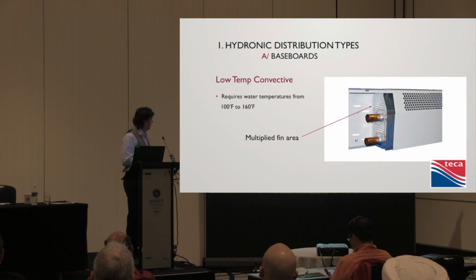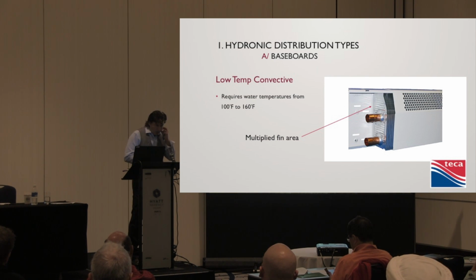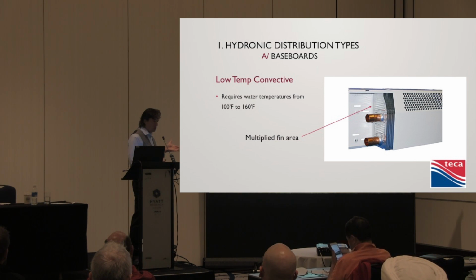Okay, and then we said, well, now that our heating appliances are becoming more efficient, in order to keep them efficient, we have to run them cold or cooler. So let's use a baseboard that maybe we can run cooler. So low temperature convective requires water temperatures from 100 to 160. So that's on the higher end. So, I mean, how do you make it so?